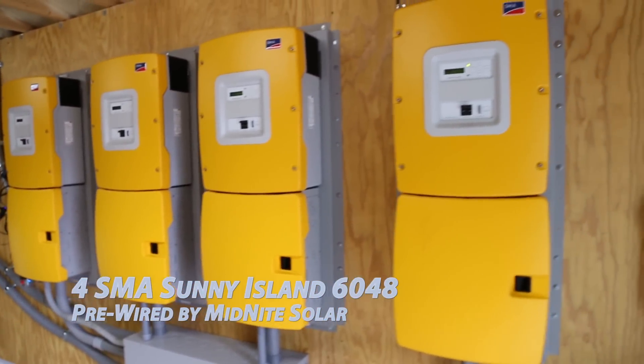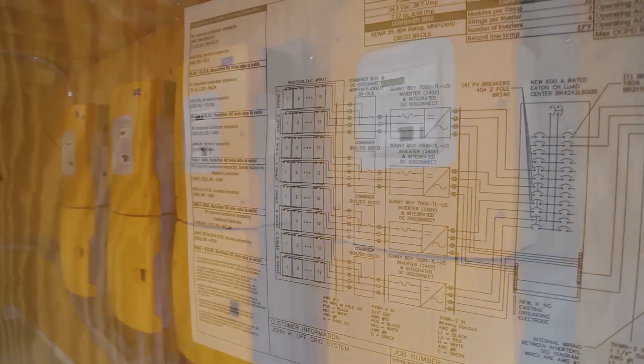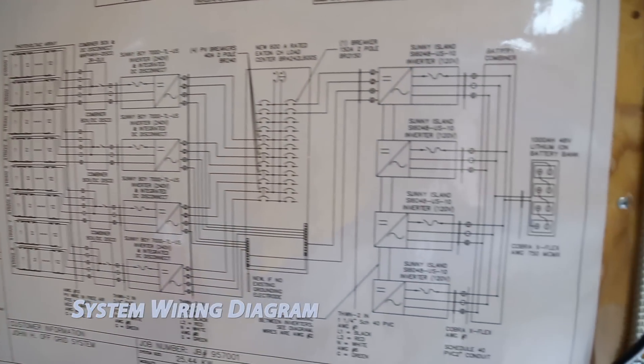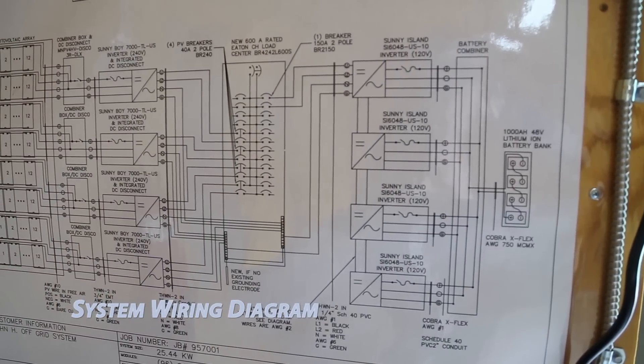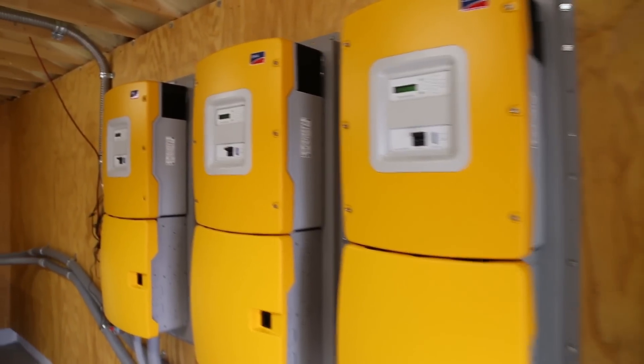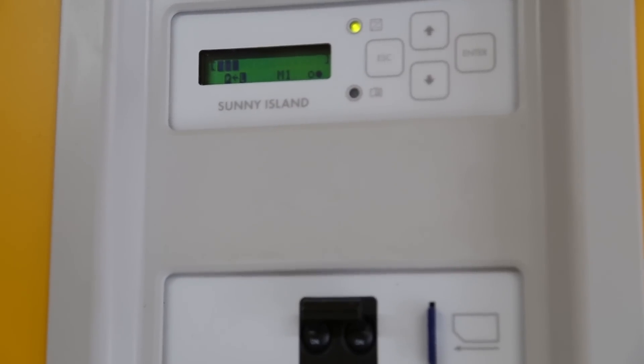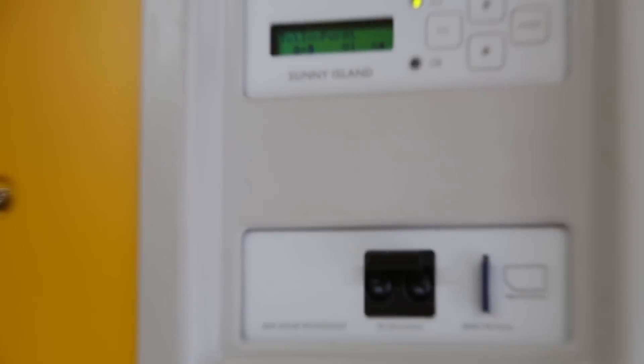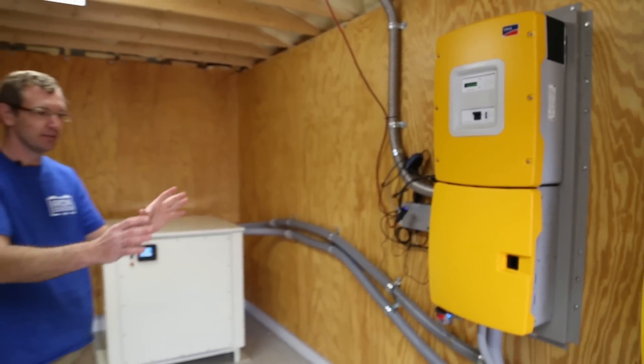Each inverter is capable of powering 6,000 watts, so we have 24,000 watts of combined output power. These Sunny Island inverters are also the main battery charger — they are responsible for drawing power from the solar and managing the charge cycle going into the battery. This system was pre-wired by MidNite Solar.